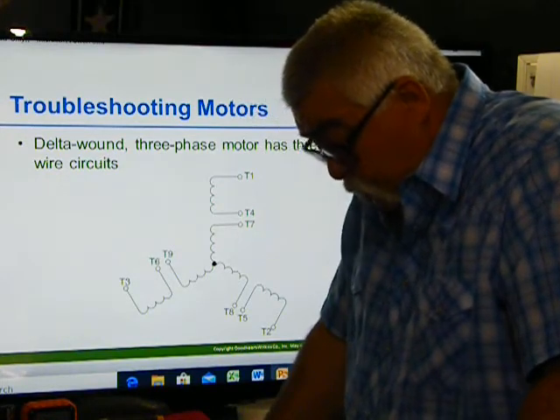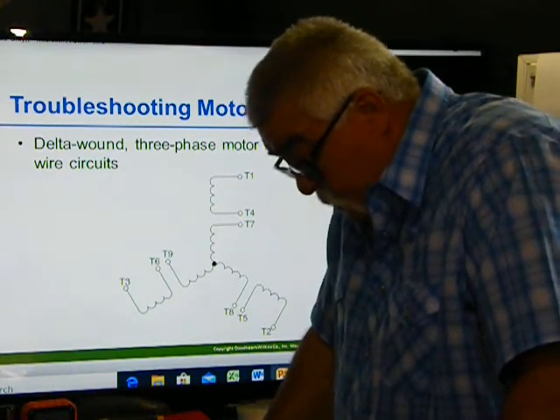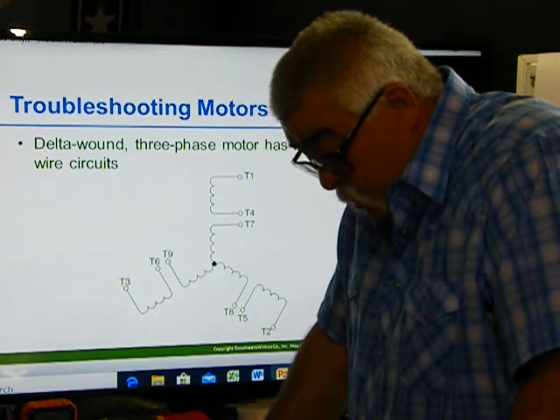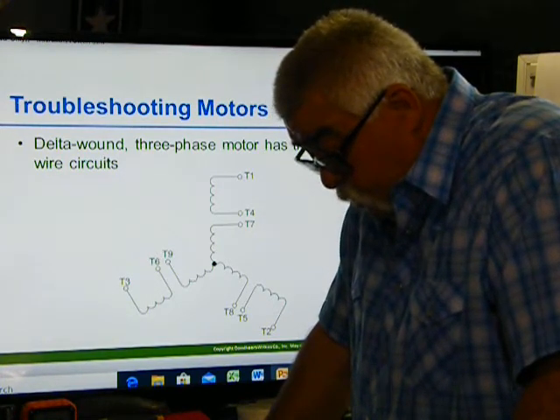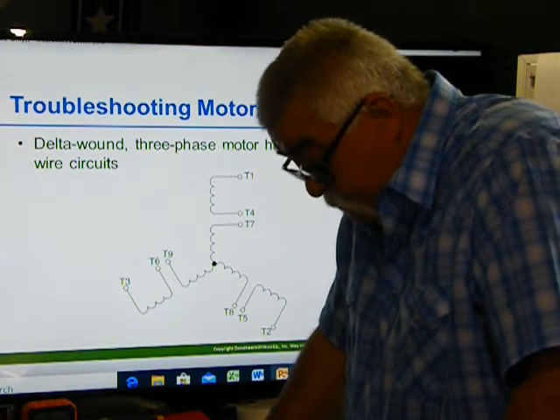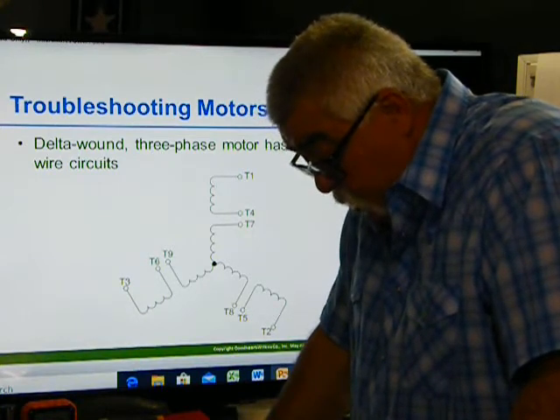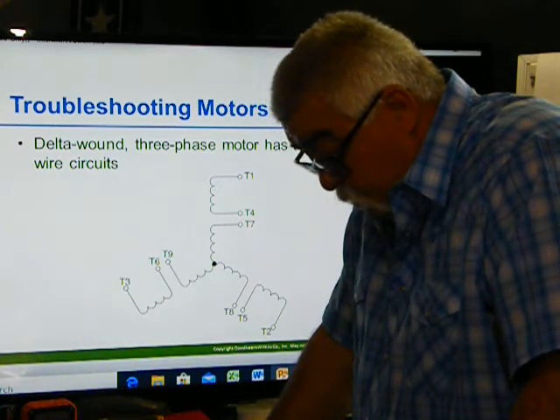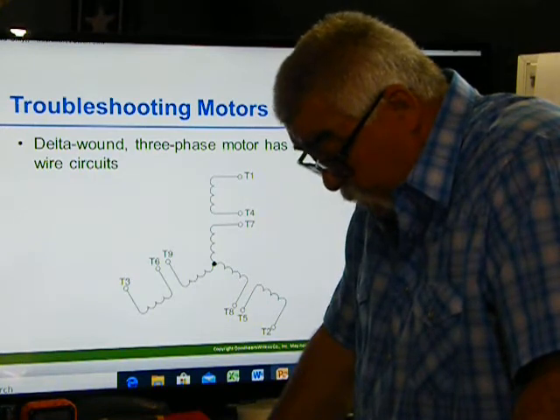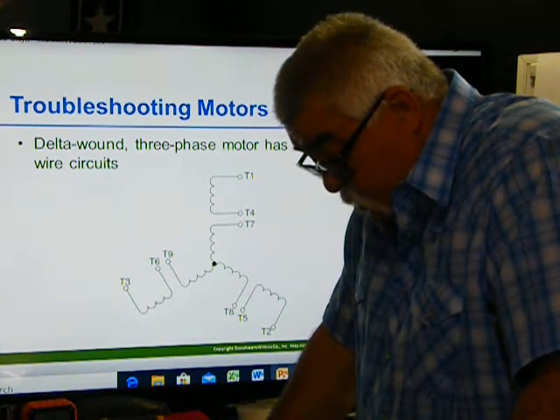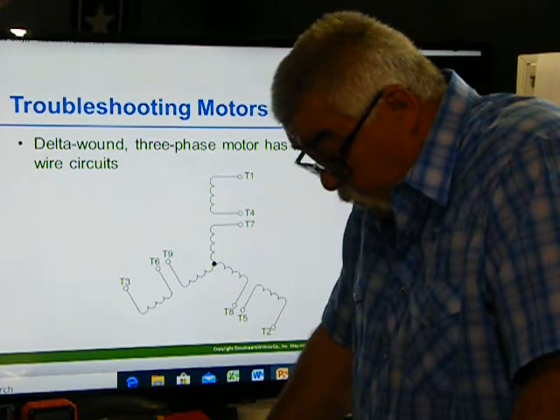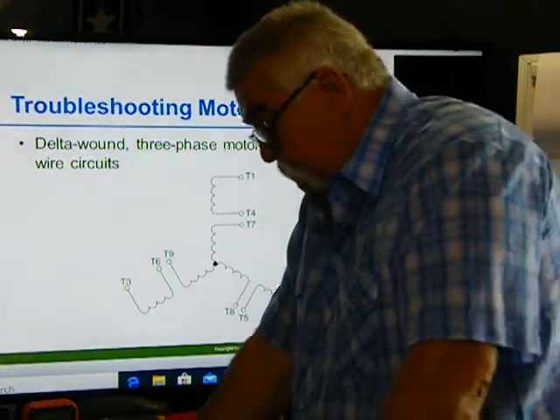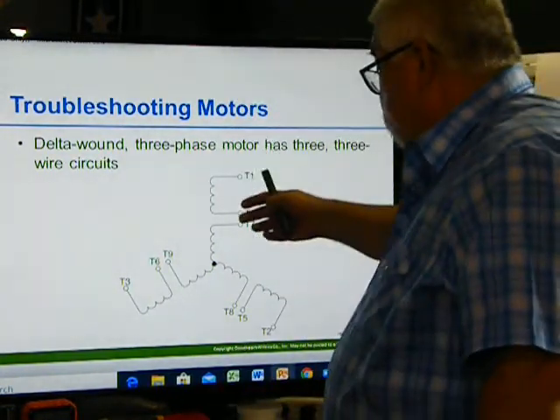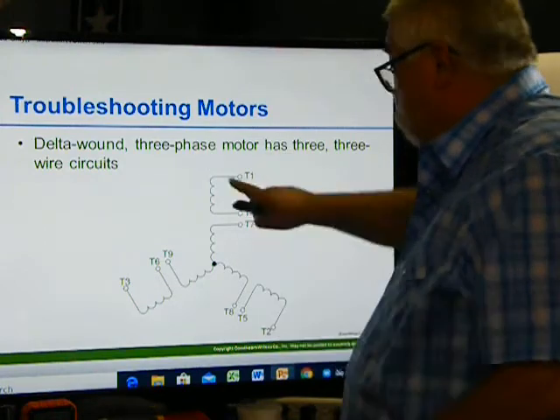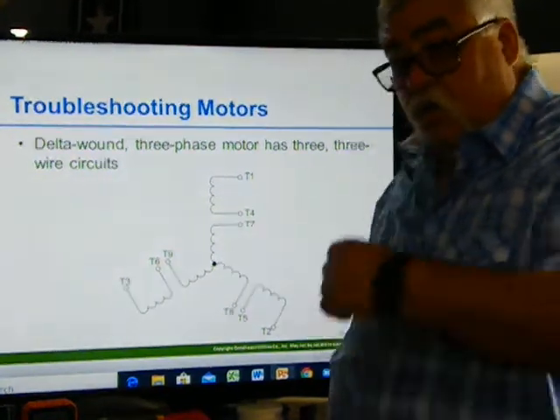Turn off power and connect terminal T1 to T7. Apply power to run the motor, and then read the voltage between T4 and T8. If the voltage reading is 330 volts to 350 volts, T1 and T4 are correctly identified. If the voltage reading is 120 volts, the labels for T1 and T4 need to be switched. So if you're reading across here, your voltage is right because it's going across this winding. As you go across that winding, it's going to increase the voltage.